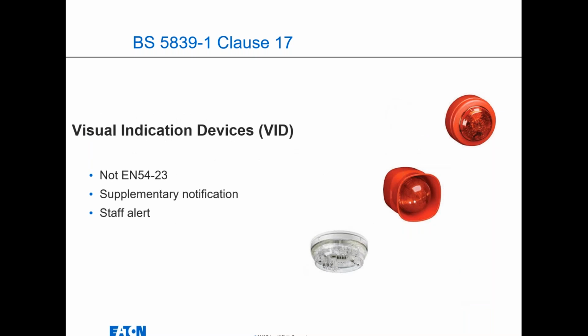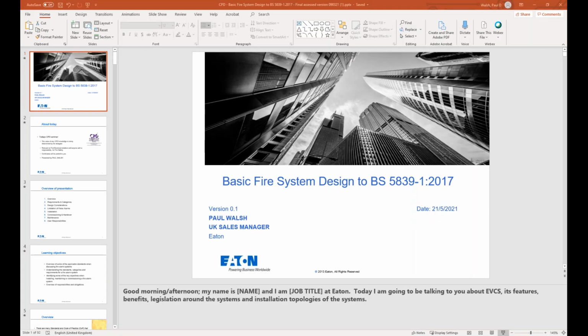But then you've also got VIDs. So just to confuse everybody, a VID is a visual indication device, as you can see. They're not EN54 Part 23 compliant, but they are EN54 compliant. And they are supplementary notification. And generally, in most buildings, you can get away with that, because if you're not using VADs as a primary means of notification, then normally it's the sound pressure levels, the sounders, that do that for you.